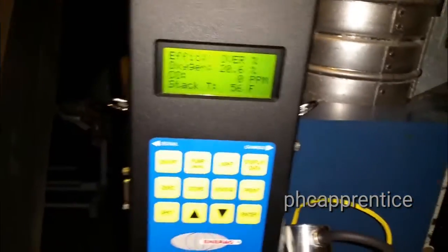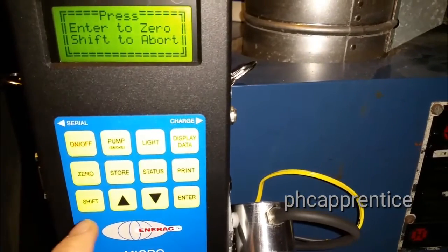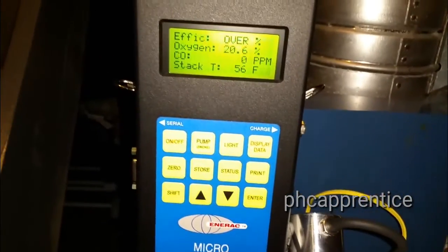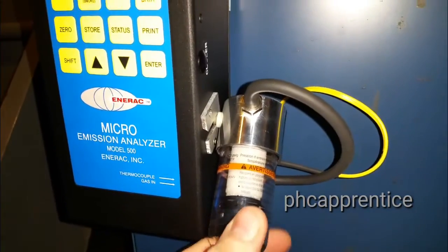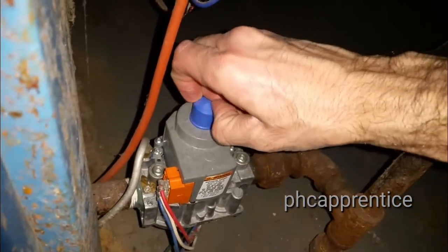For right now, since we've got 0 ppm on the Sensit P100, I'm going to go ahead and zero this out. Push enter. Gonna grab the probe. Keep the probe handy. Don't know if you can hear, it's a pretty quiet machine. It's running on 75% duty cycle right now. And I'm gonna go ahead, turn the gas valve back on. And cycle the boiler.